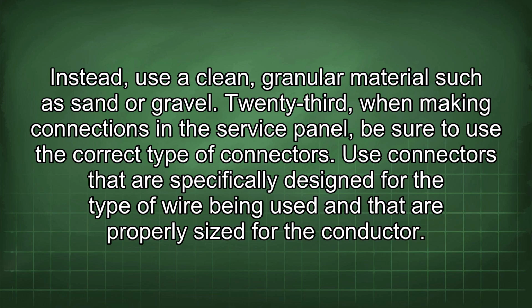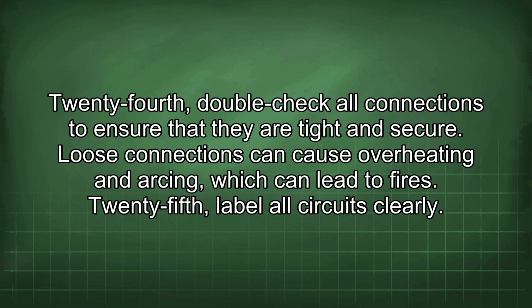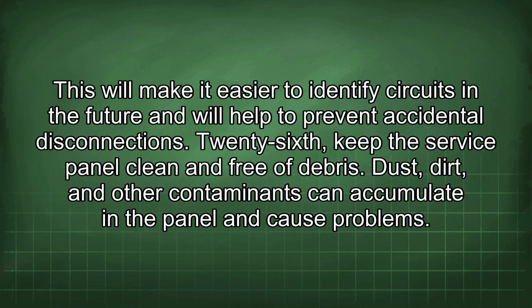23rd, when making connections in the service panel, be sure to use the correct type of connectors. Use connectors that are specifically designed for the type of wire being used and that are properly sized for the conductor. 24th, double check all connections to ensure that they are tight and secure. Loose connections can cause overheating and arcing, which can lead to fires. 25th, label all circuits clearly. This will make it easier to identify circuits in the future and will help to prevent accidental disconnections. 26th, keep the service panel clean and free of debris. Dust, dirt, and other contaminants can accumulate in the panel and cause problems.